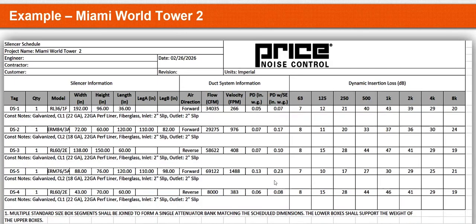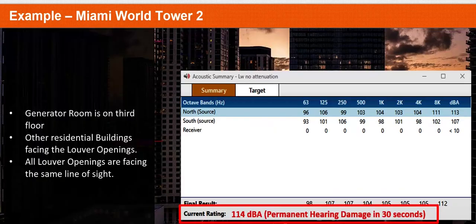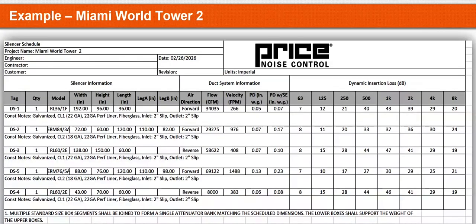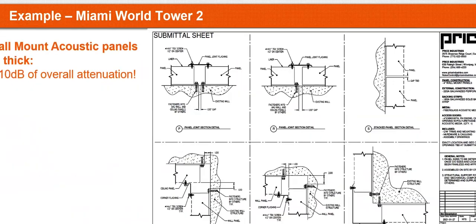The installed pressure drop has a lot to do with the setup and close proximity with other duct elements. So all that can be simulated in the same software that I was showing you initially to do the barrier wall. That's a free software to be able to size the silencers and see what the sound pressure level will be at a particular line of sight. Those acoustical panels lining 70% of the room are very important, mainly because they will prevent that sound amplification within the room, especially on those hard corners. A 4-inch thick panel covering 70% of the room could easily boost your performance overall as it travels through different paths towards the openings within the room, up to 7 decibels of added attenuation.